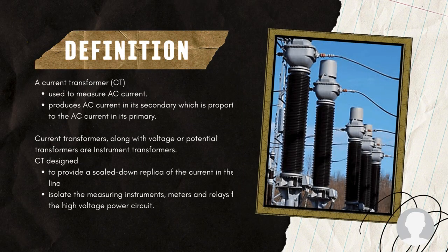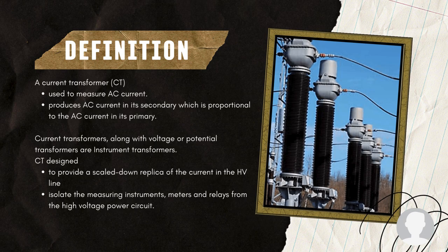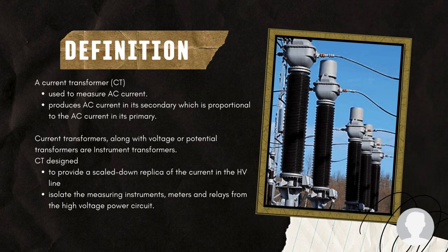A current transformer, CT, is used to measure AC current. It produces an AC current in its secondary which is proportional to the AC current in its primary. Current transformers, along with voltage or potential transformers, are instrument transformers. Current transformers are designed to provide a scaled-down replica of the current in the high-voltage line and isolate the measuring instruments, meters, and relays from the high-voltage power circuit.